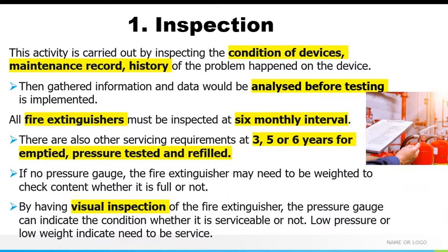If for example some of the fire extinguishers don't have a pressure gauge, sometimes they need to make sure that the content is enough to be effective to fight the fire. And also visual inspection is very important. You need to check the hose, you need to check the nozzle. Sometimes somebody plays around with the safety pin, and so on. So it's very important to check.